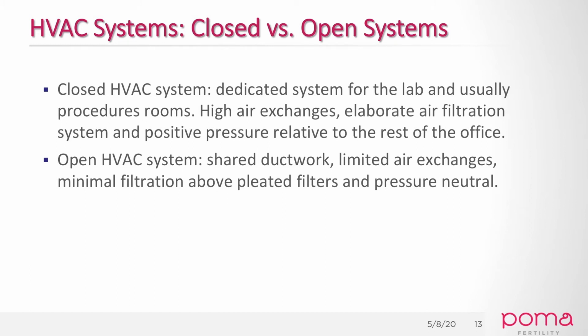Now let's turn our attention to HVAC systems. I'll break them into two basic types: closed systems and open systems. Closed HVAC systems are more common now, characterized by high air exchanges, elaborate air filtration, and positive pressure relative to the rest of the clinic. Open systems are found more in older settings, often in office IVF labs. What they have in common is shared ductwork, limited air exchanges, minimal air filtration, and usually neutral pressure relative to other rooms.